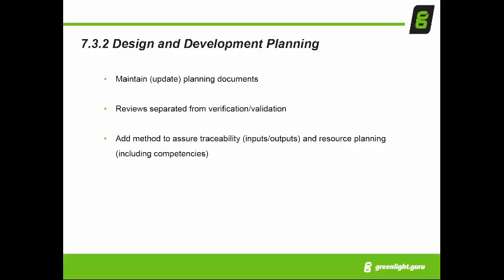Design and development plan. Now there are a number of these clauses that I'm going to go into specifically under design and development. The main design and development clause is 7.3. And then there are a lot of subclauses that fit under that 7.3 umbrella that have all changed. If you're speaking FDA, FDA refers to design and development as design control. So for everything that I'm talking about today, design and development and design control are considered synonyms.